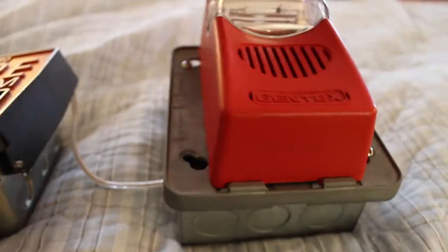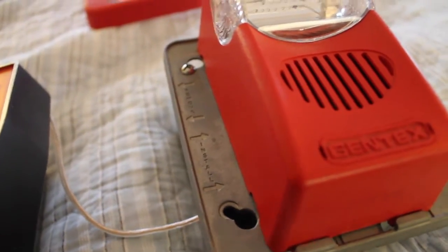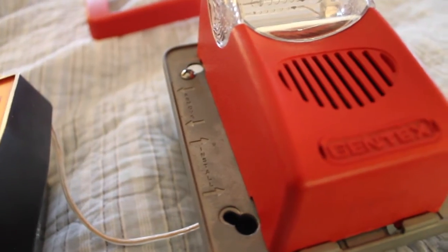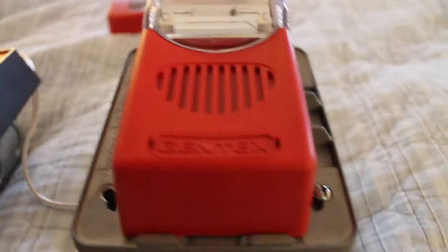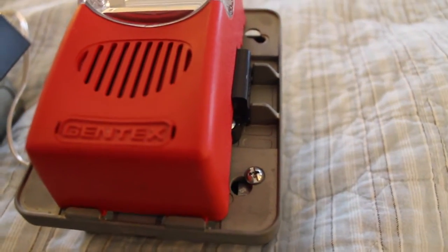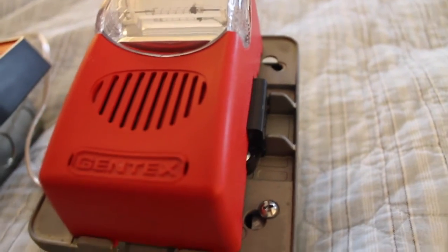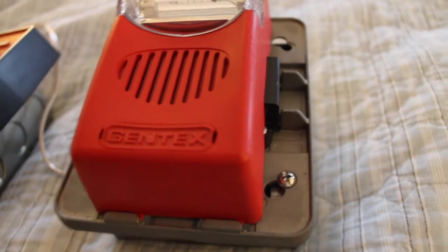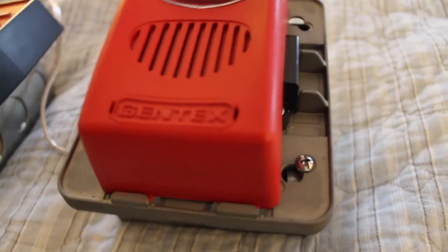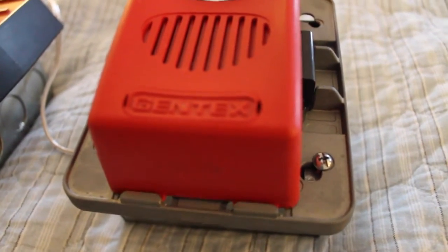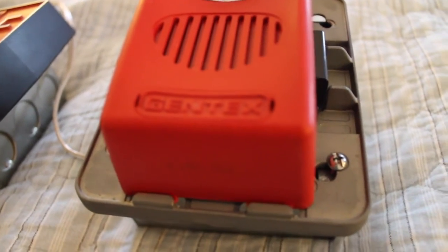Now, let me pop this thing off so I can show you some stuff underneath here. Normally, the candela indication switch would be right here. If it was a Commander 3, it would be the switch. If it was the Commander 2, I think it would be just a static number. Normally, you would have your dip switches over here for tone selection. But interestingly enough, that's actually on the back of the device. I might have shown this in the Fire Alarm Collection video. Your dip switches are actually on the back of the device. And thirdly, there's only two types of tones that are available. The horn and the tone. None of the fancy whoop, chime, like on the Commander 3 I showed you. So, there's that. Let me just put this back on.